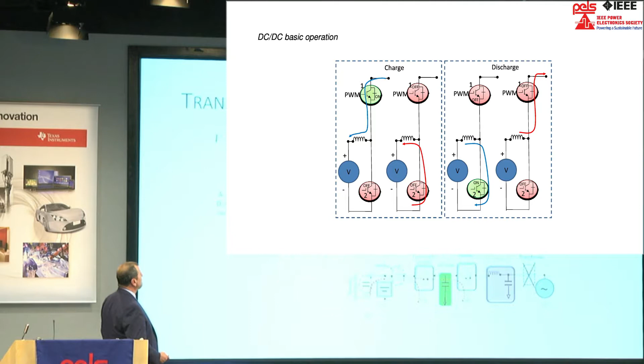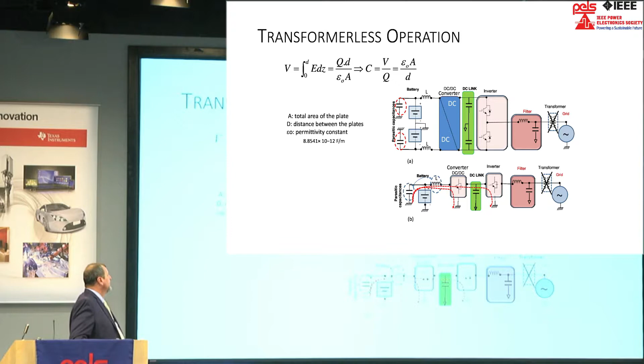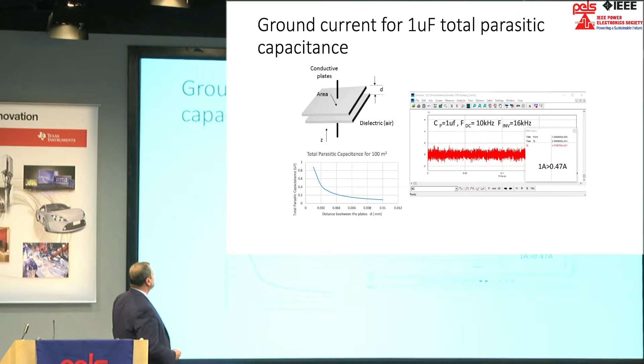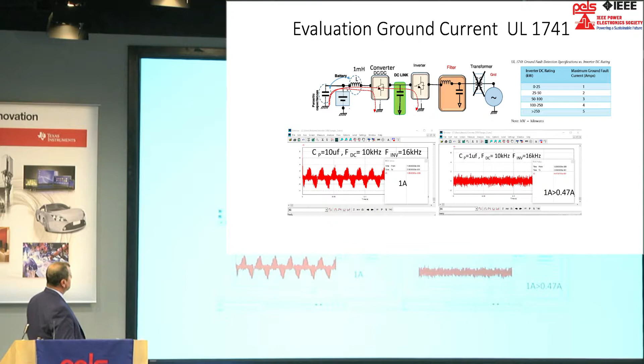This one is a transformerless DC-DC converter. When you build a transformerless inverter, you have other issues, because you have to avoid the current that goes to ground, in order to meet standards, which is limited, for example depending on the size of the inverter, in this case less than 1 ampere. You have to run all the proper simulations to verify the ground currents stay below 1 ampere. For inverters of 25 kilowatts, it can go up to 5 amperes for bigger inverters, but you have to avoid the paths to ground being too high.